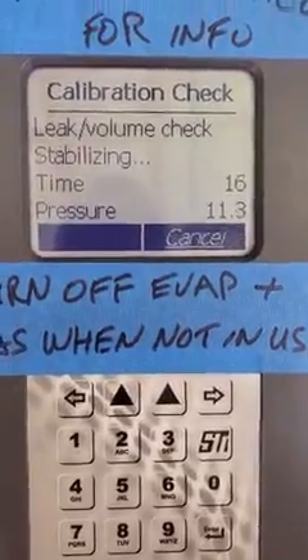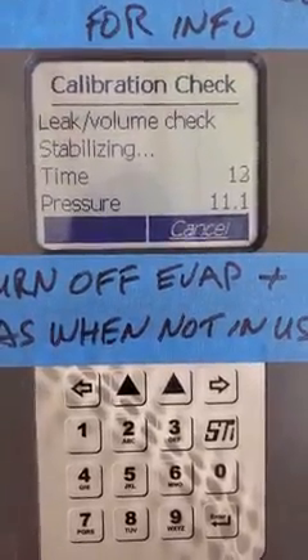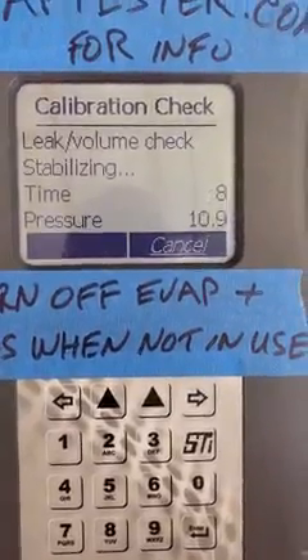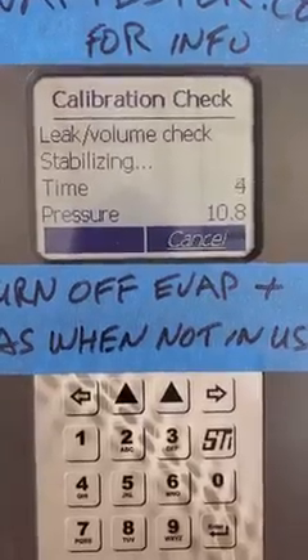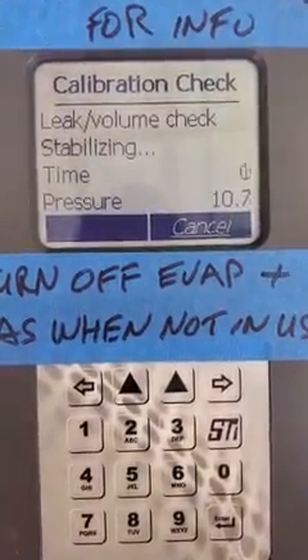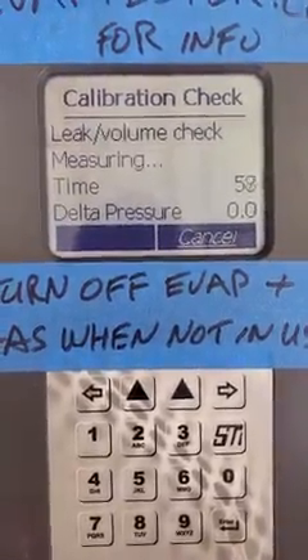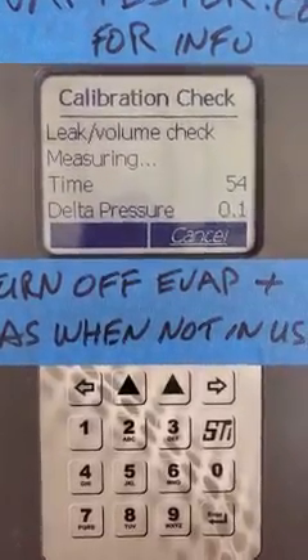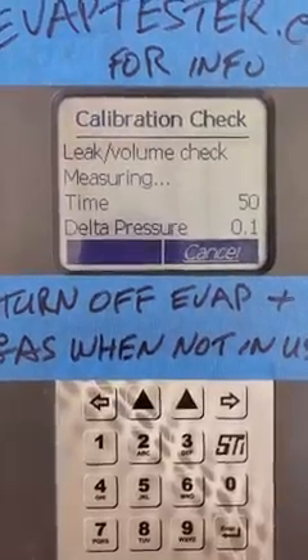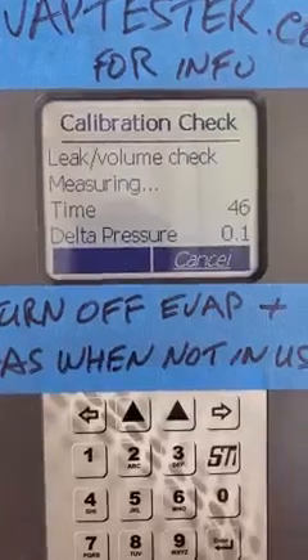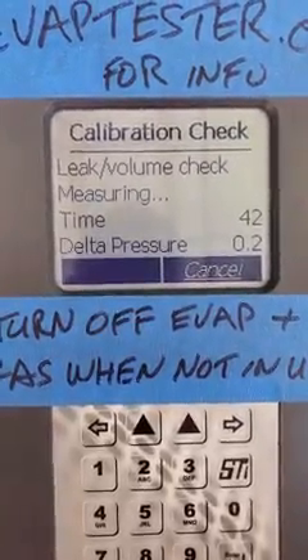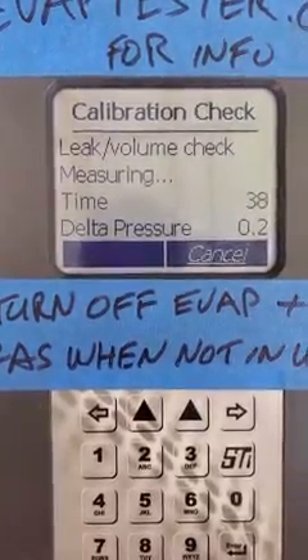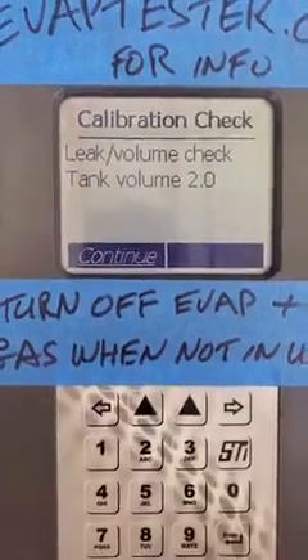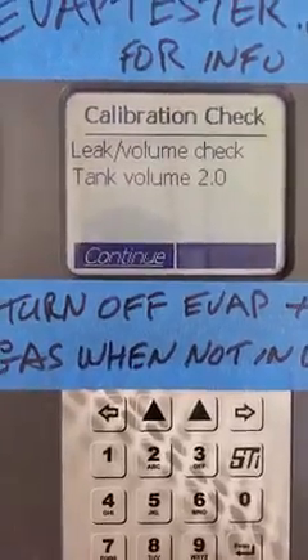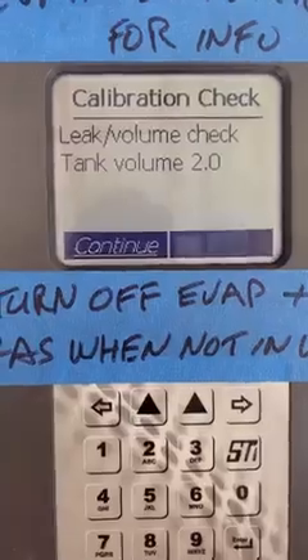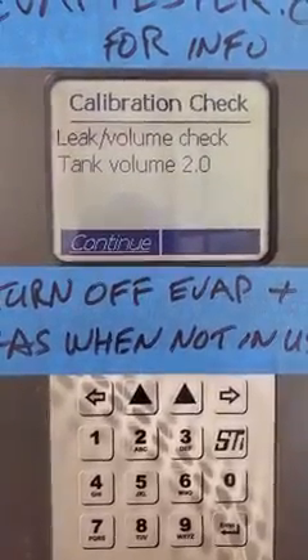The pressure, you will usually start at about 16, 15 and count down. As long as it stays above 10, the machine will pass the tank. Now the machine's moved on to check the delta pressure. Delta pressure will count up from 0.1 up to usually about 0.7, 0.8. If it goes all the way to 1.0, it will fail. The tank volume, as you can see, says 2.0. Anywhere from like 1.7 to 2.3 would be normal. 2.0 is where we're actually heading for.